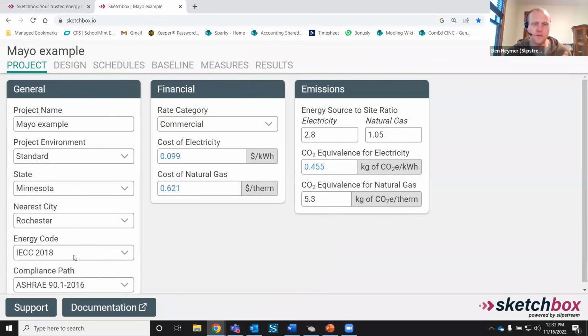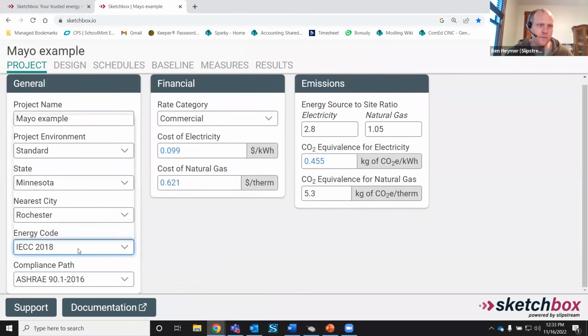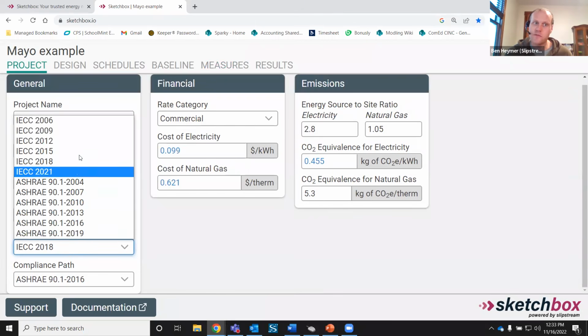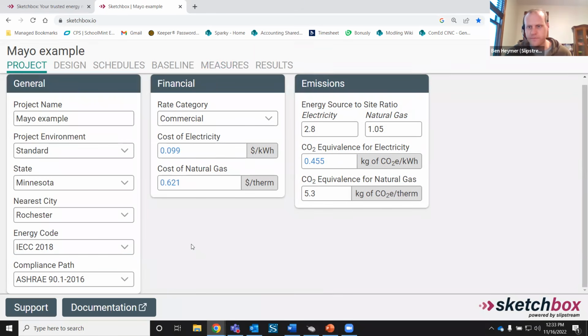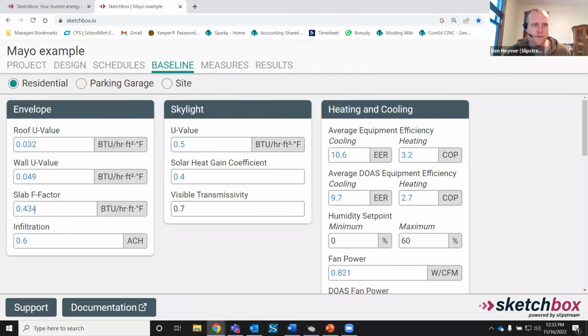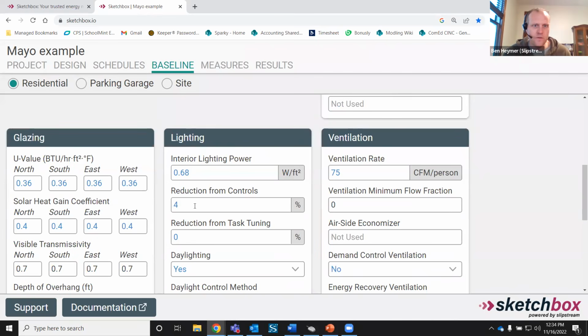Here we're using the latest energy code. If you were working with an older building, I would start with an older code like IECC 2006 or ASHRAE 2004, or whatever code you thought was appropriate, and use that as my starting point. Then I'd spend time adjusting my baseline values to represent that building as closely as I can, which might involve calculating U values for whatever wall system is there, plugging in values from the nameplate of the HVAC equipment, or just some reasonable assumption. You can tweak a lot of this stuff.